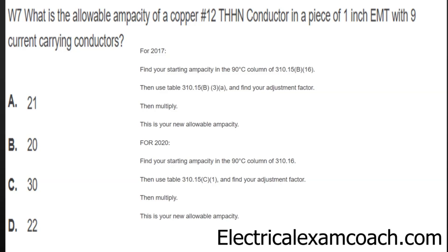Then you're going to use table 310.15(B)(3)(a) to find your adjustment factor. Then all you have to do is multiply. When you multiply that out, that's your new allowable ampacity of this conductor. In this case, the answer ends up being A.